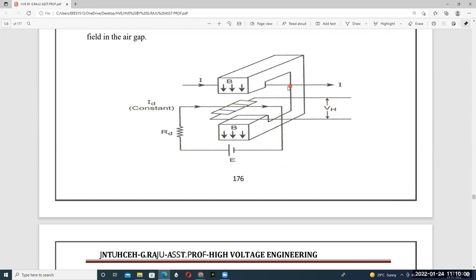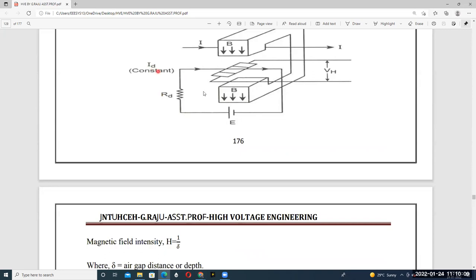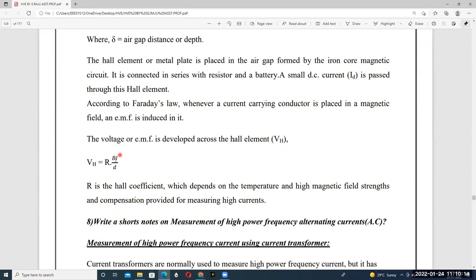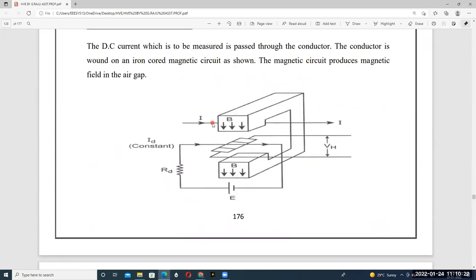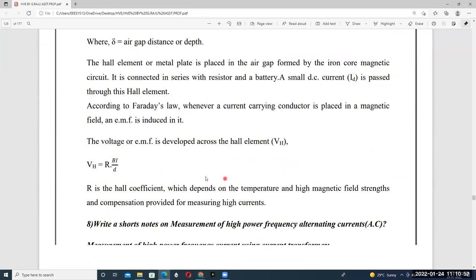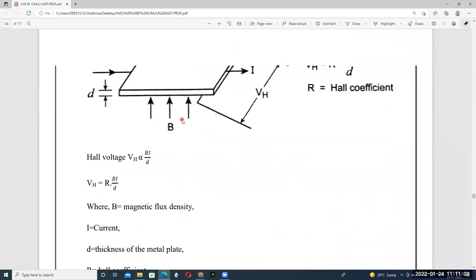The Hall voltage is proportional to the magnitude of the current. Here I is the current flowing through the conductor — the high DC current which is to be measured. Id is the constant battery current. Since the current-carrying Hall element is placed in the magnetic field, a Hall voltage Vh is induced that is proportional to the current I. In this way we can measure very high values of DC current using the Hall generator.